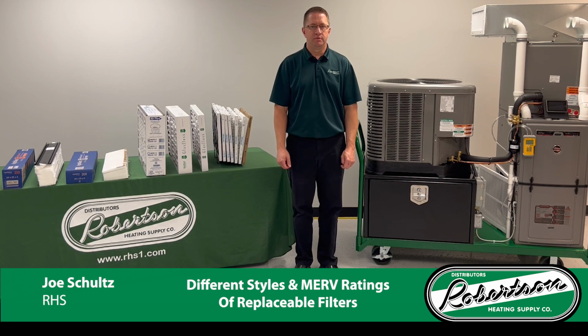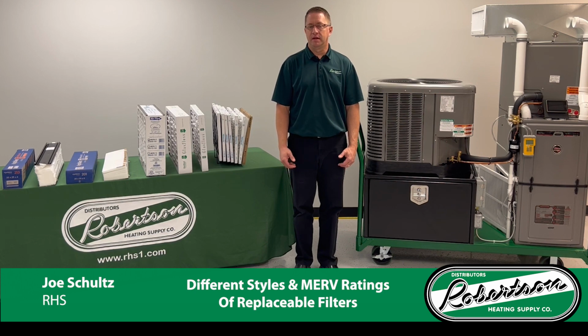Merv ratings 13 through 16 filter down to particle sizes of 0.3 to 1 micron. Includes everything I mentioned before, plus bacteria, tobacco smoke, and copier toner. Applications include hospital patient care, general surgery, and smoking areas.